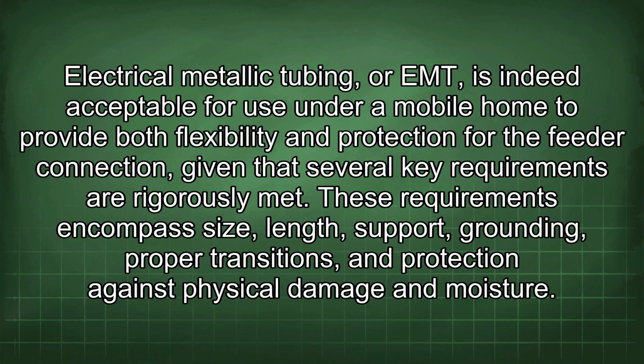Electrical metallic tubing, or EMT, is indeed acceptable for use under a mobile home to provide both flexibility and protection for the feeder connection, given that several key requirements are rigorously met. These requirements encompass size, length, support, grounding, proper transitions, and protection against physical damage and moisture.